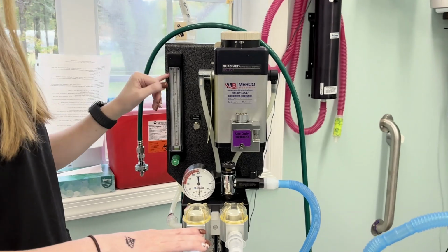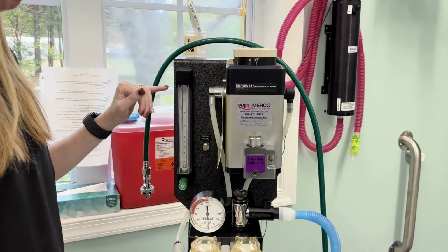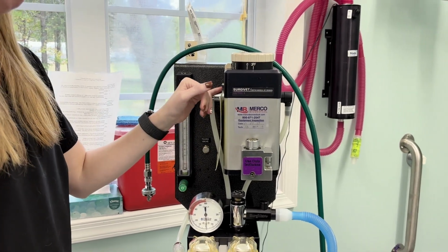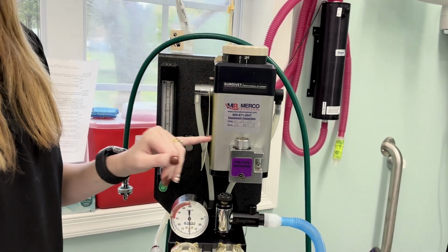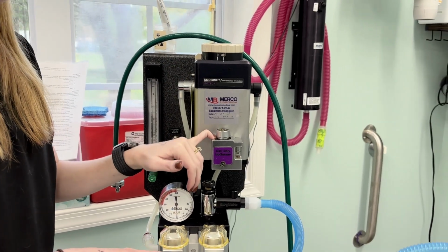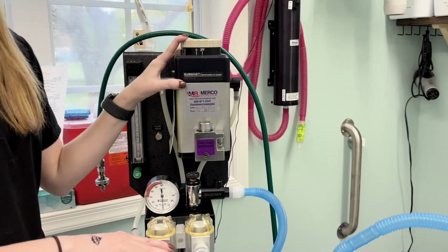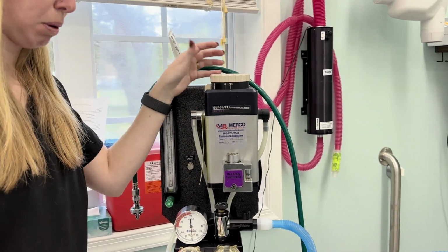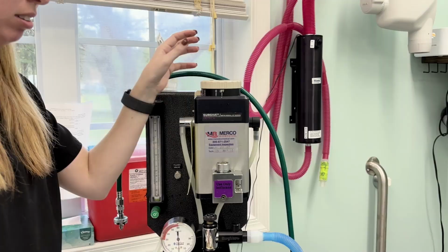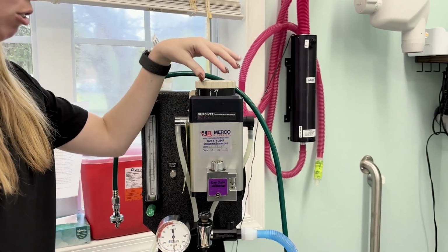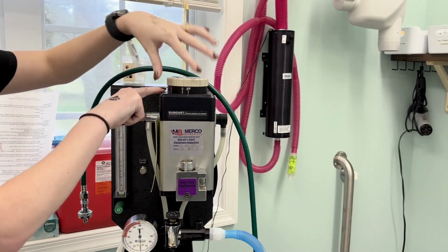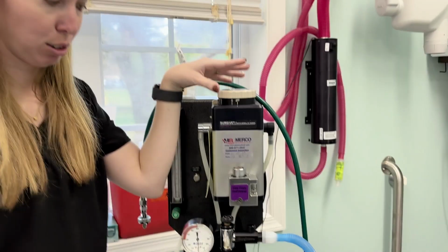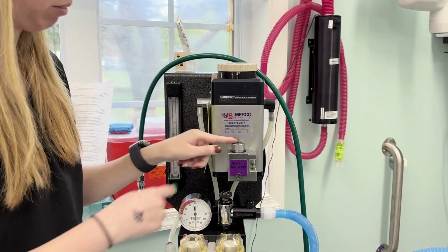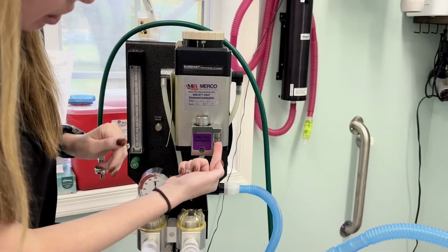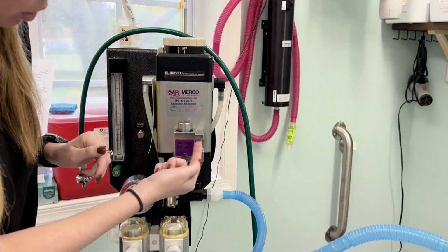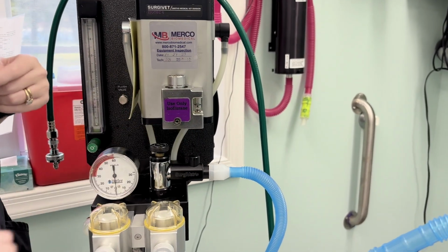Next, there is a line that goes from the oxygen to our vaporizer, and that vaporizes the liquid isoflurane that we use. This vaporizer controls the amount of ISO, or the amount of anesthetic gas, that the patient gets. You would click this button and just turn it, and that'll control the gas pretty quickly. Over here is where you fill up the isoflurane, and you want the level to be in between the two arrows.